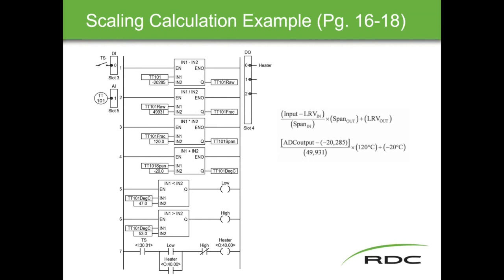In the heater control logic: if temperature switch one is closed and the low temperature bit is true and the high temperature bit is not true, the heater turns on. When the temperature rises to 53°C, the high temperature coil energizes, breaking the rung and turning the heater off.